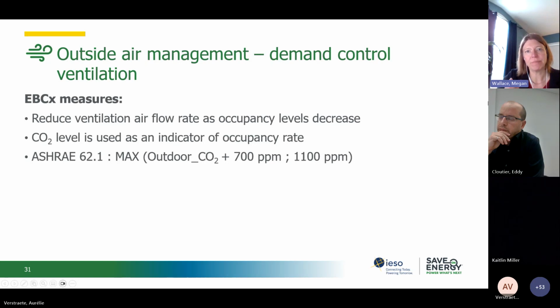The next measure we can look at is demand control ventilation, which would reduce the ventilation airflow rates as the occupancy levels decrease. We use CO2 monitors to determine what the occupancy rate is. ASHRAE 62 says that it's the outdoor CO2 plus 700 parts per million, to a maximum of 1100 parts per million.